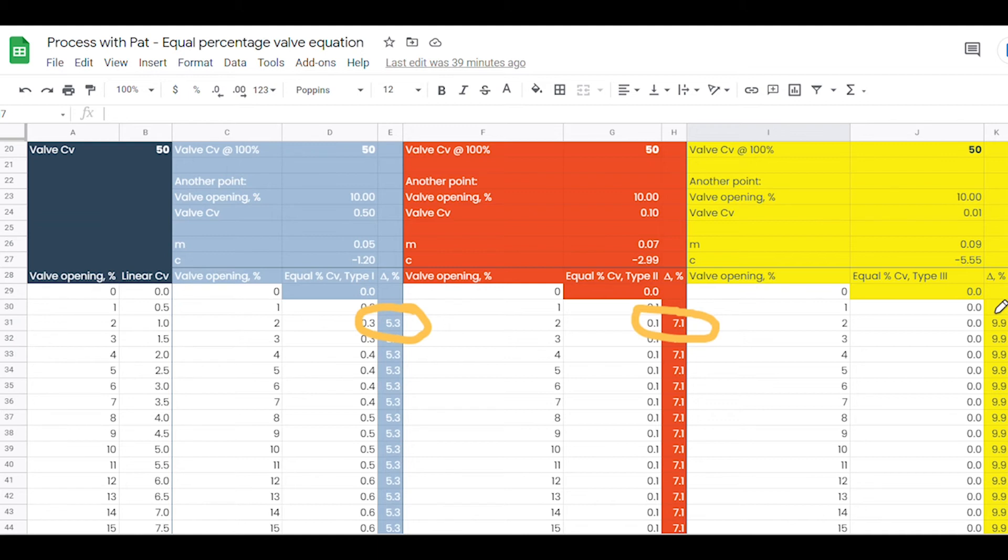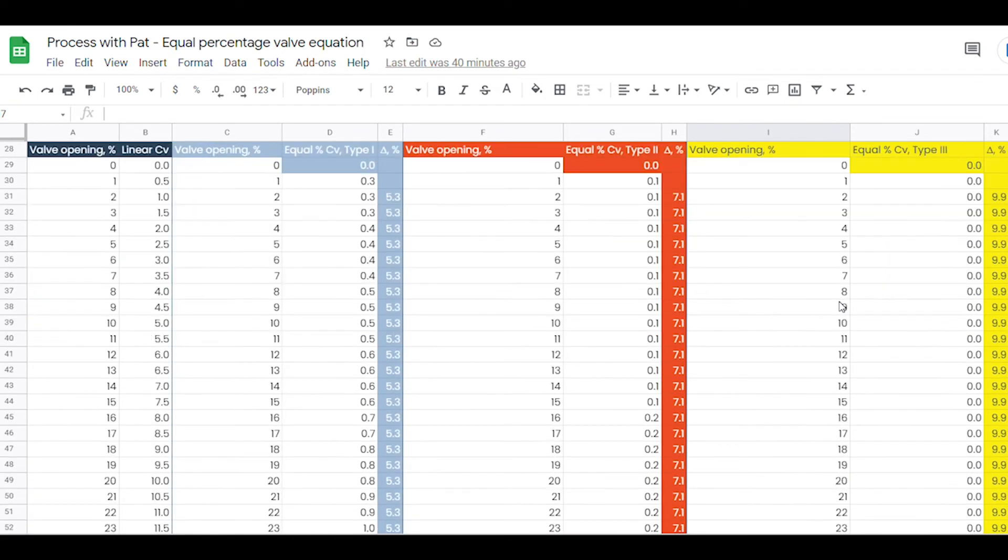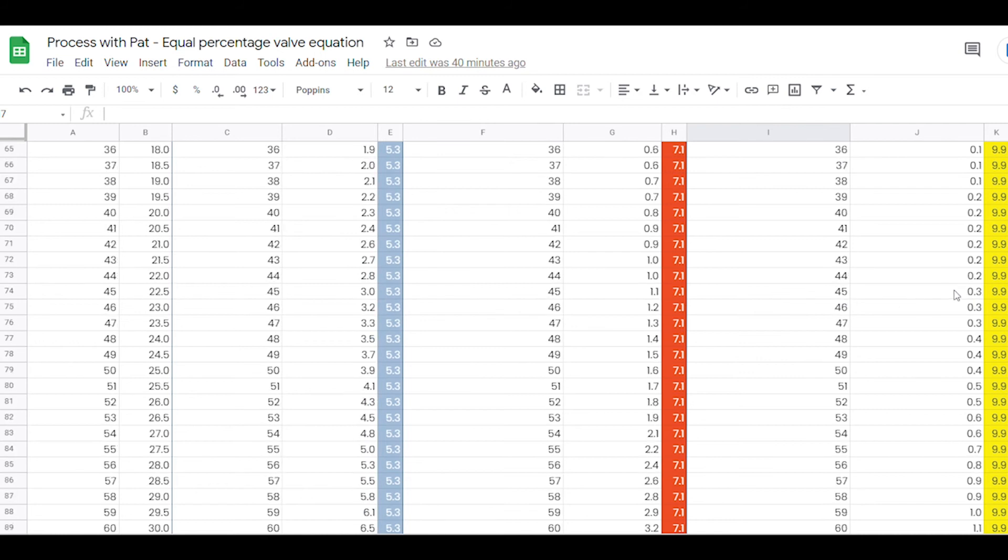And finally the third valve increases the flow by 10% for every additional percentage opening. You can see that this percentage is constant as the valve opens to 100%.